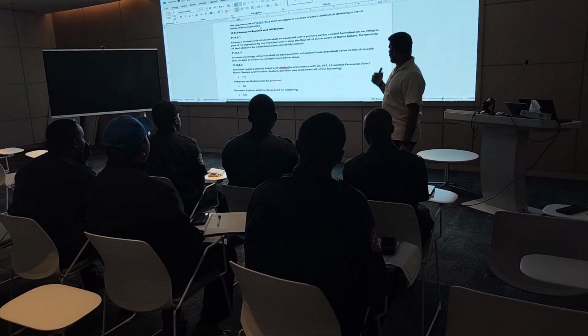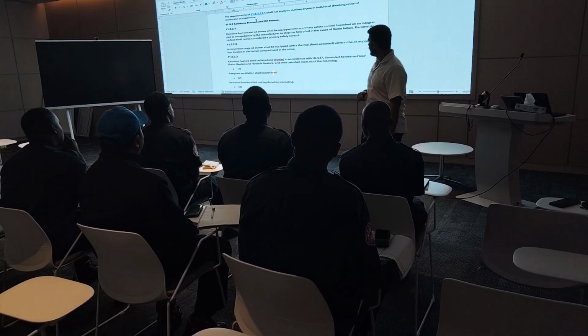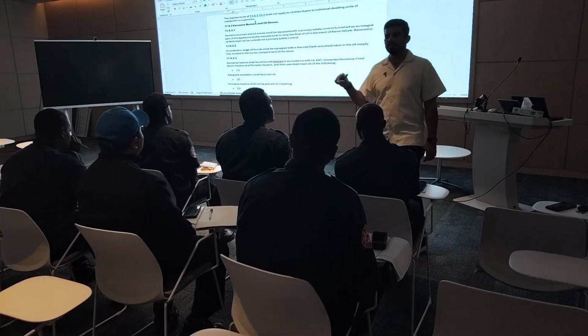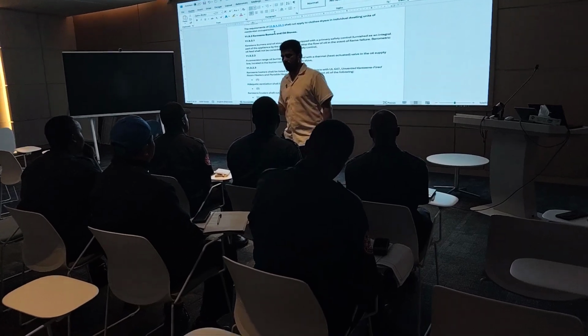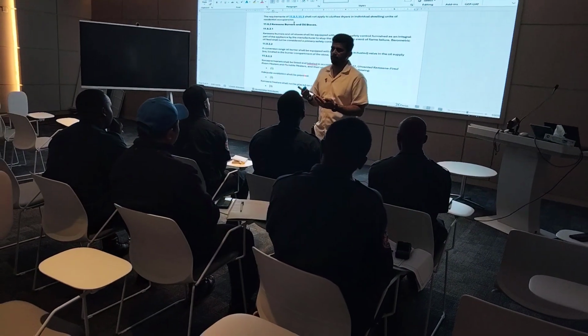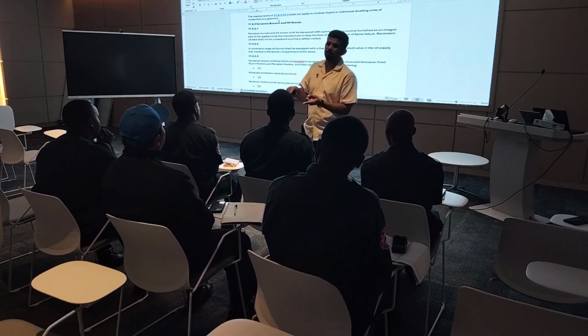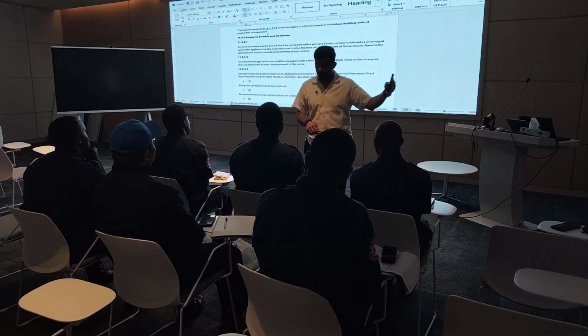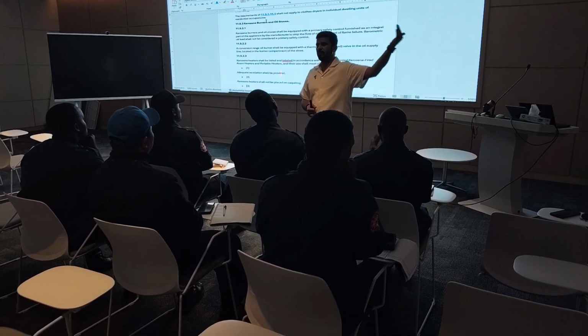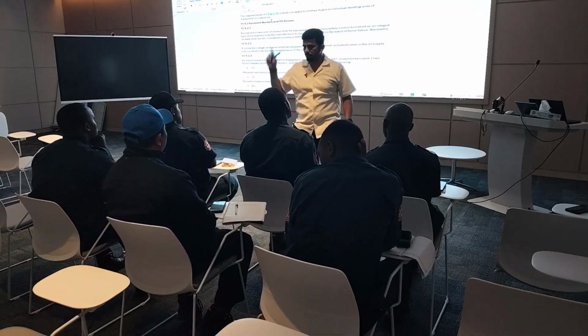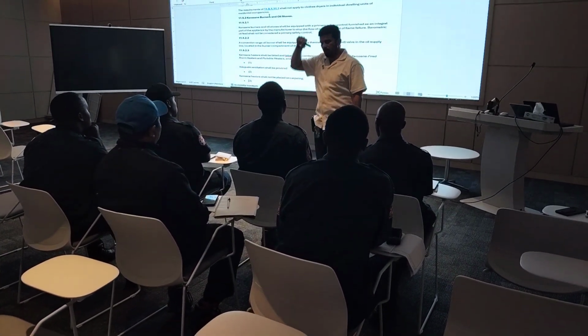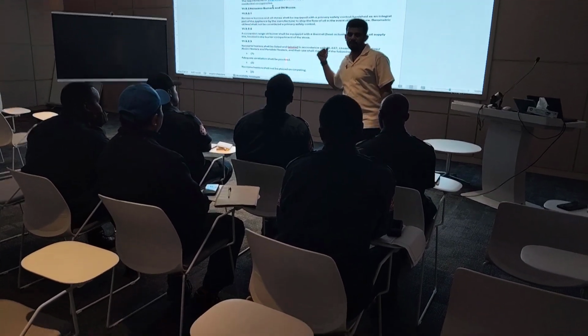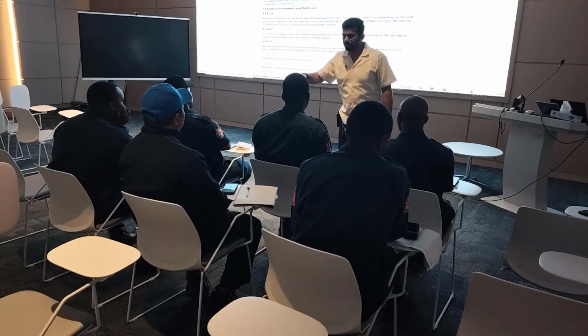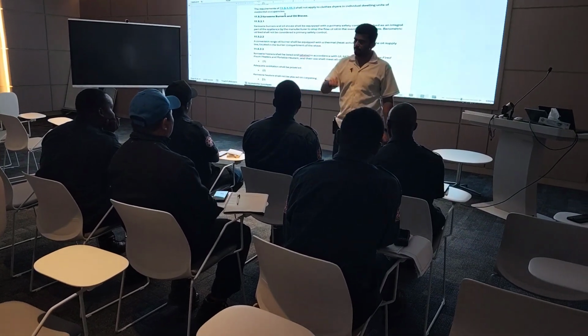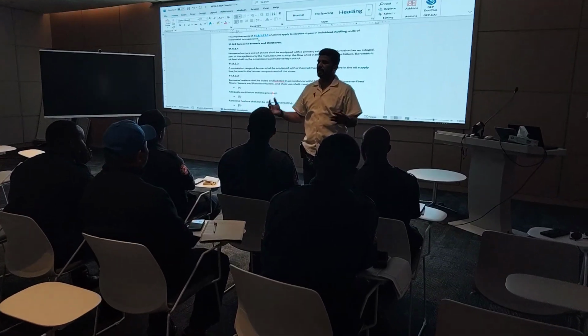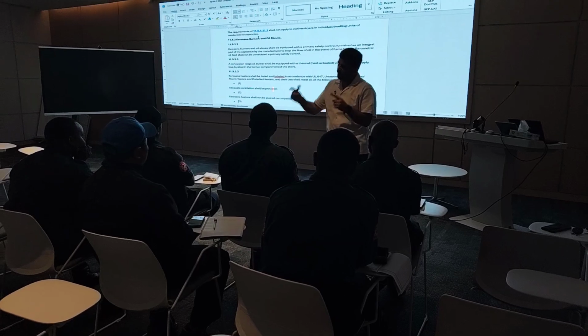A commercial range oil burner shall be equipped with a thermal heat actuated valve in the oil supply line. See, everything mentioned here is for the manufacturer. When we are going to install, understand, the NFPA code is a higher code. It's not for the thing that we have. Let's suppose we purchased a hyperbaric chamber and we received it. Now is the time we have to follow all the codes according to NFPA, for the installation of the hyperbaric chamber. The safety measures for a hyperbaric chamber include a fire extinguishing system and a special system installed inside the hyperbaric chamber as per NFPA.